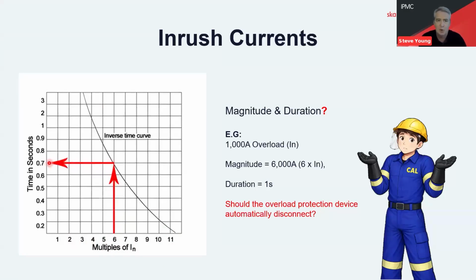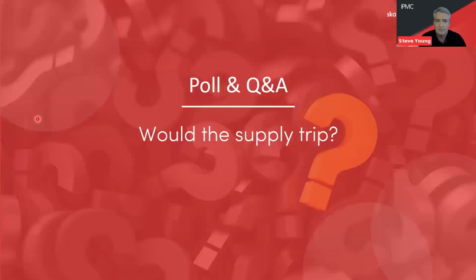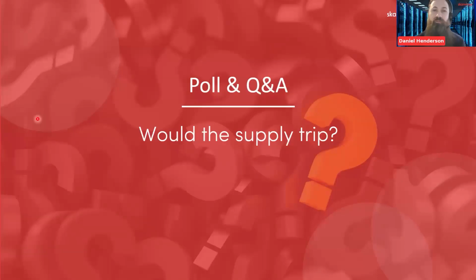So we can pose a question to you within the poll now. In an instance where we have a 6000 amp event, a magnitude of 6000 amps, but an extended duration of 1 second, should the overload protection device automatically disconnect? And that's your poll question. It's a bit of a callback really to the electrical coordination and protection and fault levels webinar we did in November. So hopefully we talked through the inverse curve and trip characteristics.